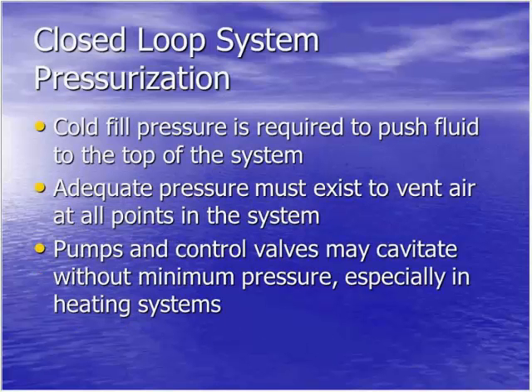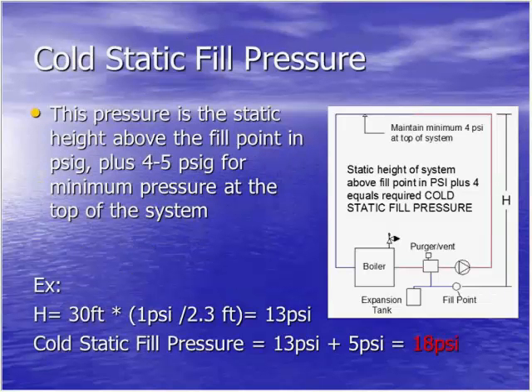Closed loop system pressurization. Cold fill pressure is required to push fluid to the top of any closed system. This adequate pressure must exist to vent air at all points in the system. Circulators are there simply to circulate the water around, whereas cold static fill pressure is to maintain that static fill pressure to push fluid to every point in the system to maintain that positive pressure. And if you don't maintain that positive pressure at all places, pumps and control valves may cavitate. And this is especially evident in heating systems where the water is obviously warmer than typical atmospheric temperatures.